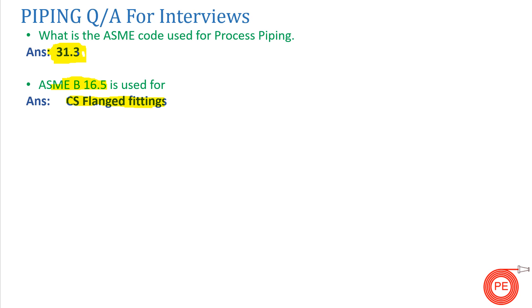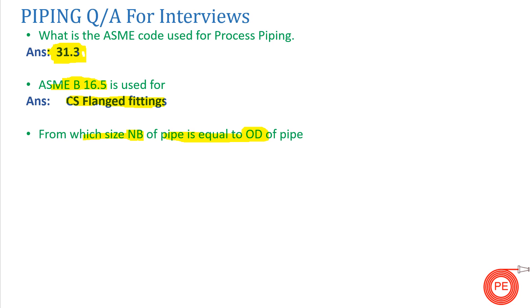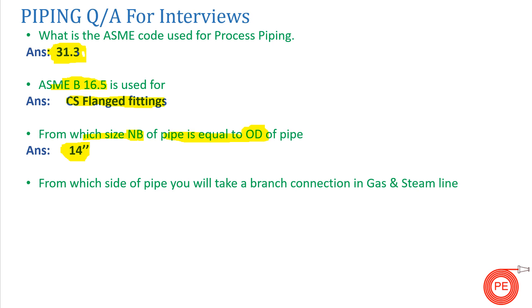The next question is: from which size does the nominal bore (NB) of a pipe become equal to the outside diameter (OD) of the pipe? The nominal bore is not equal to the outside diameter up to a certain size. From 14-inch size, or DN 350, the OD of the pipe becomes equal to the nominal bore.